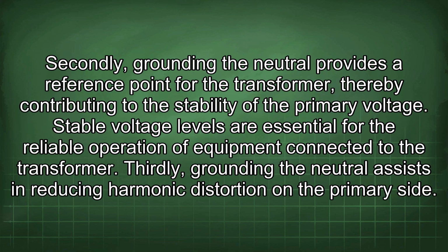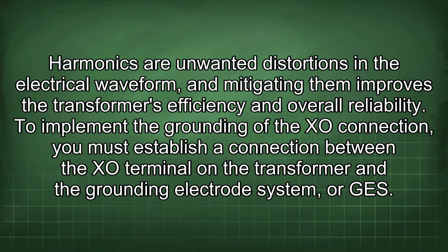Secondly, grounding the neutral provides a reference point for the transformer, thereby contributing to the stability of the primary voltage. Stable voltage levels are essential for the reliable operation of equipment connected to the transformer. Thirdly, grounding the neutral assists in reducing harmonic distortion on the primary side. Harmonics are unwanted distortions in the electrical waveform, and mitigating them improves the transformer's efficiency and overall reliability.